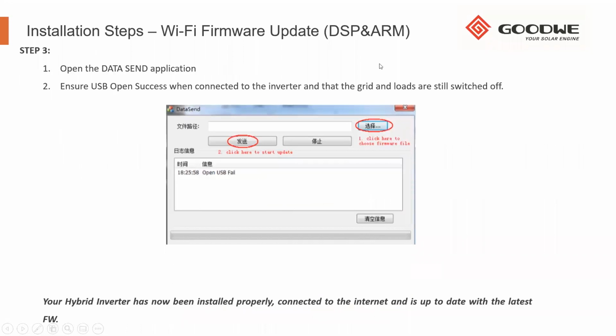First, we're going to do the data send application. This can actually be done while the unit is in full swing. It does not reboot the inverter. It doesn't affect the power controllers of the inverter. So the data send is a very nice and easy update. And like I said, some inverters that are on a very old firmware won't be able to be updated remotely, and they may have Wi-Fi on site. Then all that is needed is to do the data send on the inverter, which will then update the ARM chip of the inverter. So if this is updated, then we'll get a much better connection to the portal, and then we can follow up and do the remote update for the DSP.